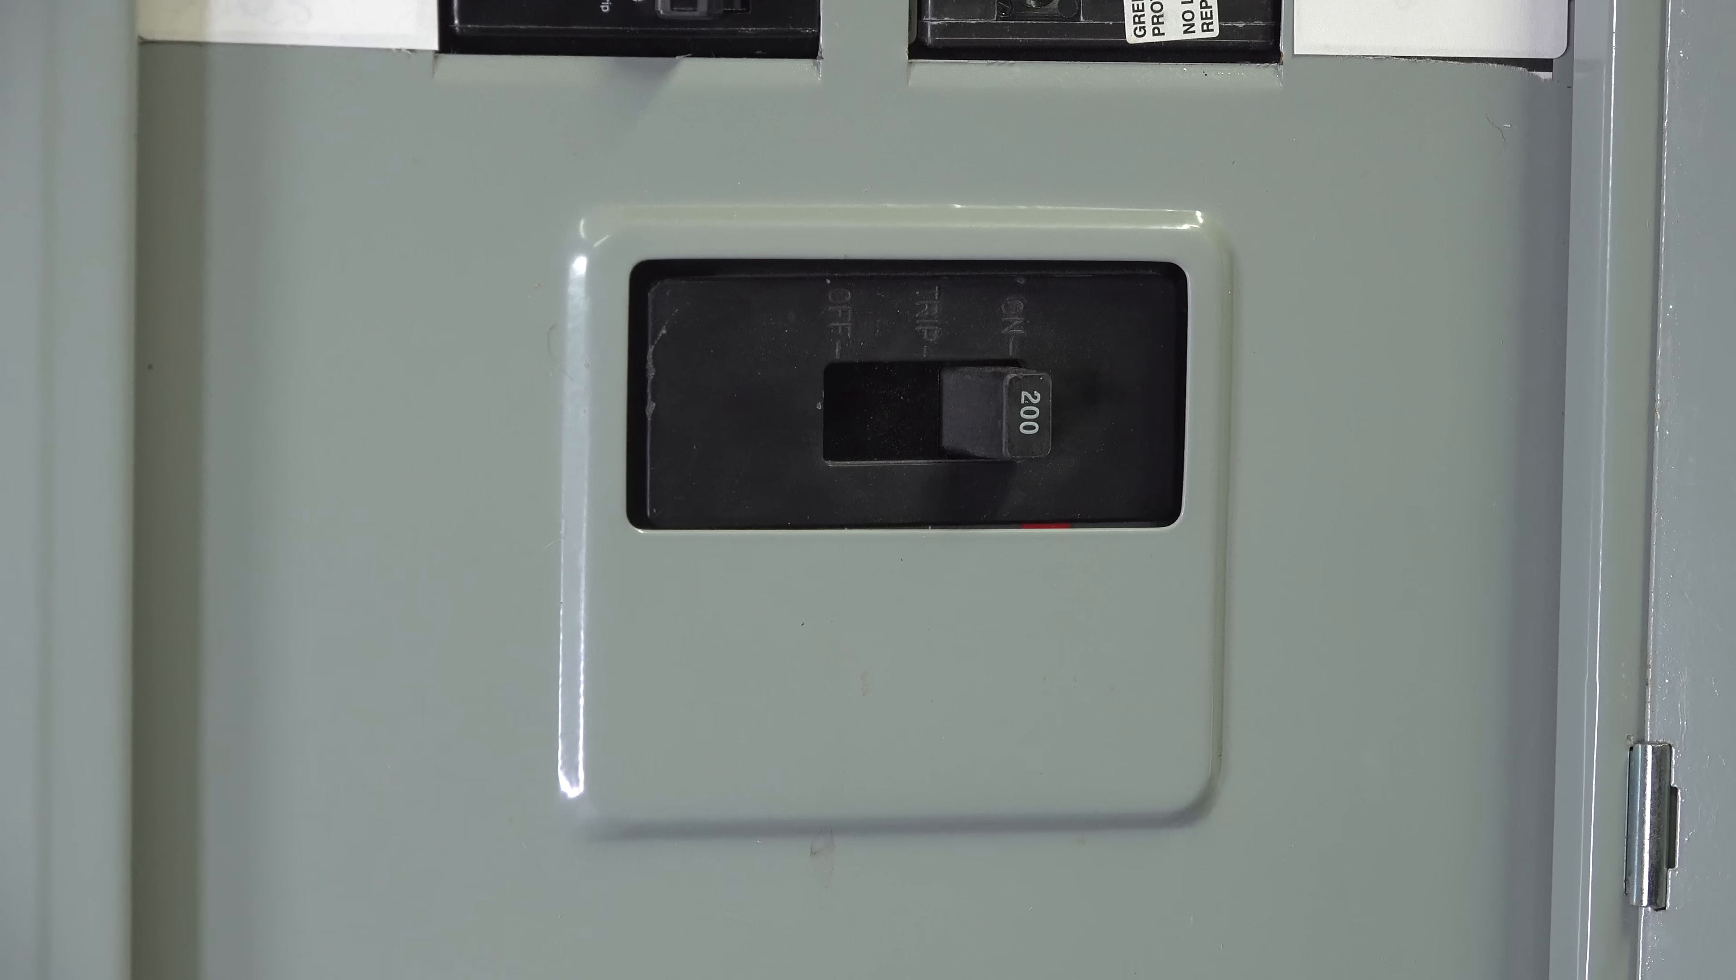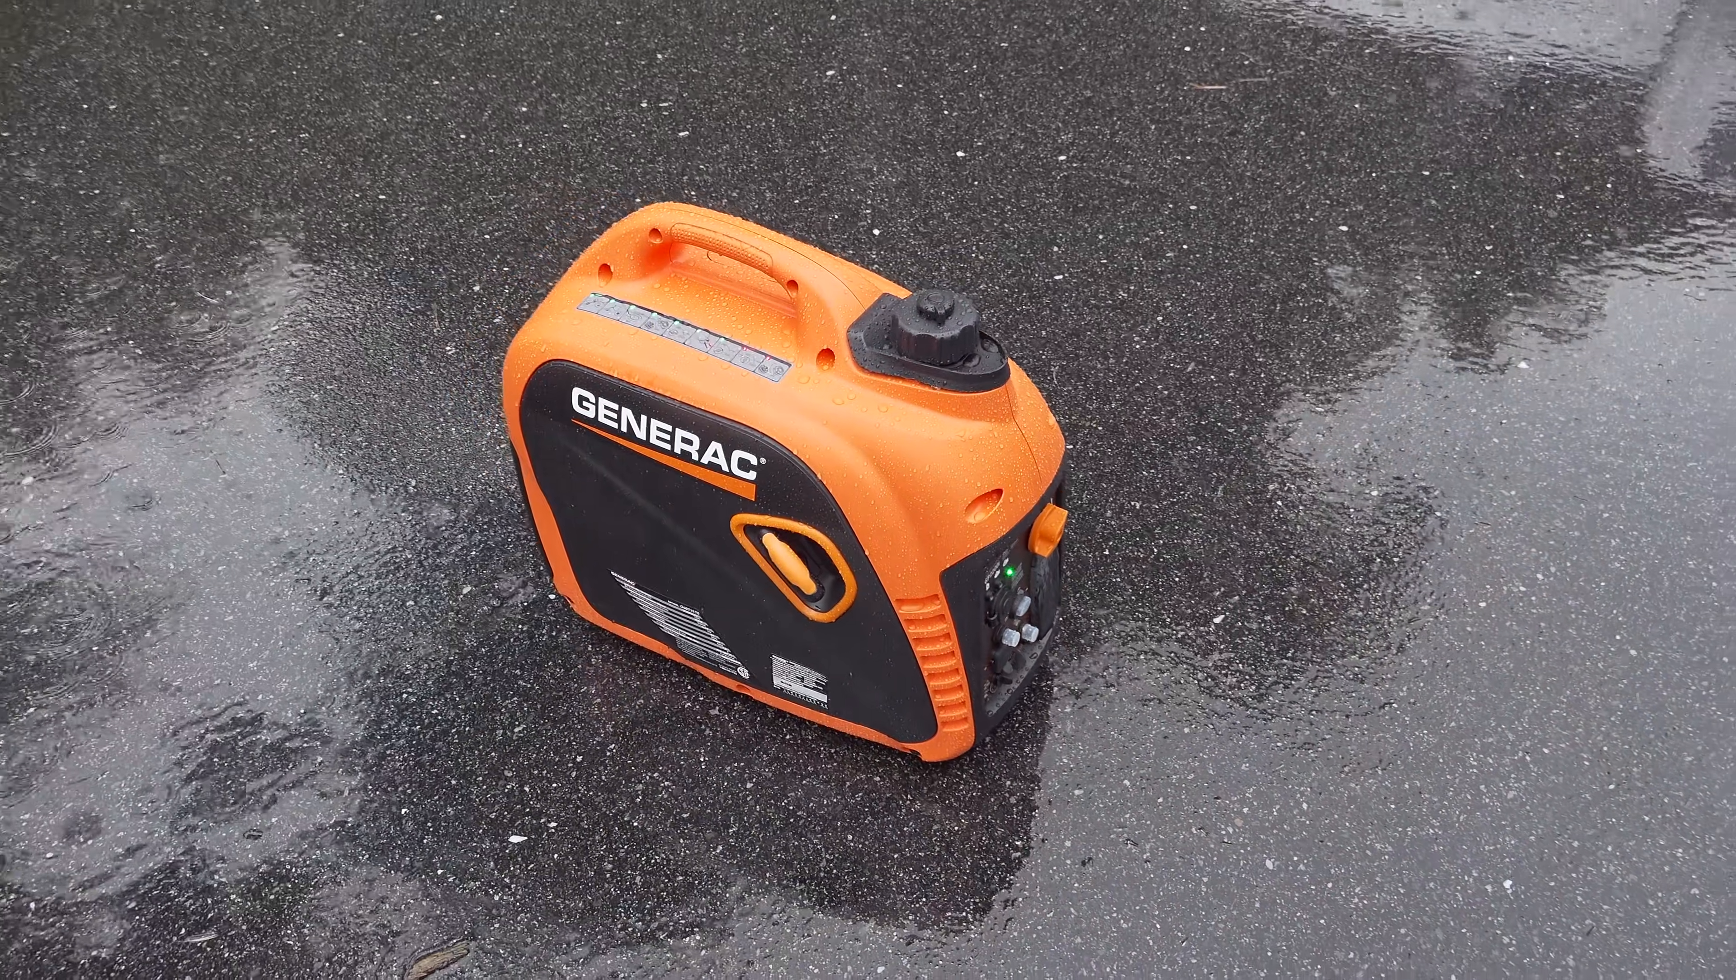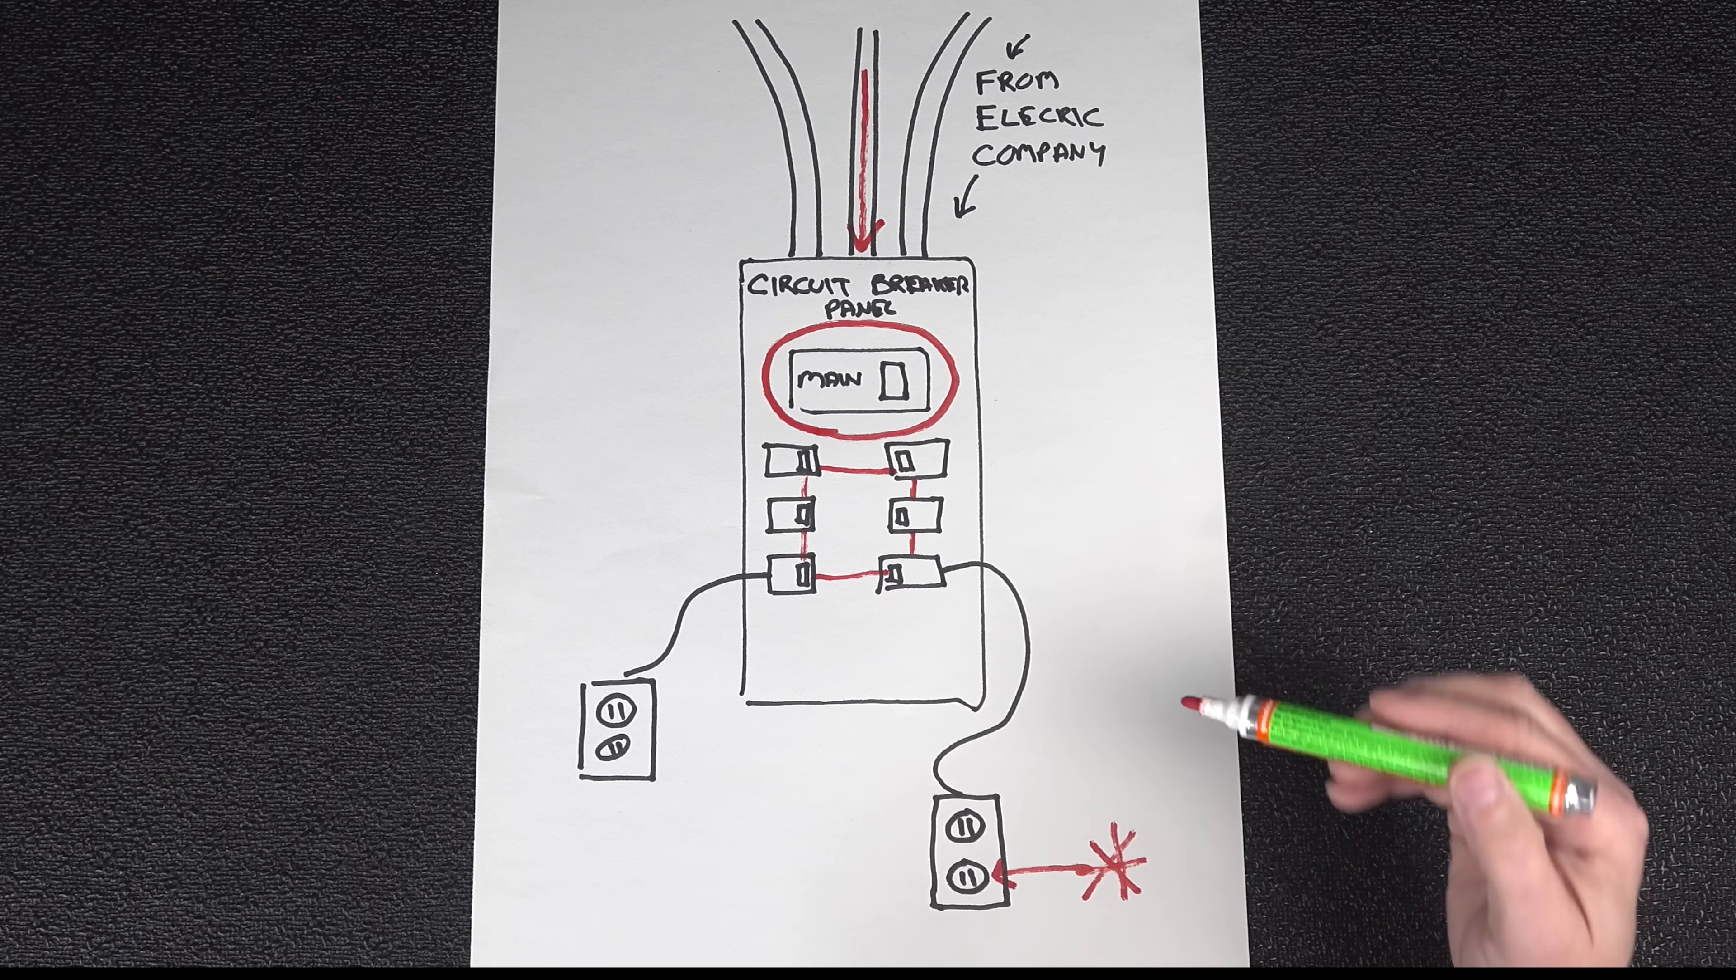So why not just backfeed your panel and turn your main breaker off? Well, that sounds like a good idea. But unfortunately, during a power outage or a storm, oftentimes people forget to do something. Or someone else in your house turns that breaker on and they could actually allow electricity into your panel causing your generator to short out and maybe even have a fire.